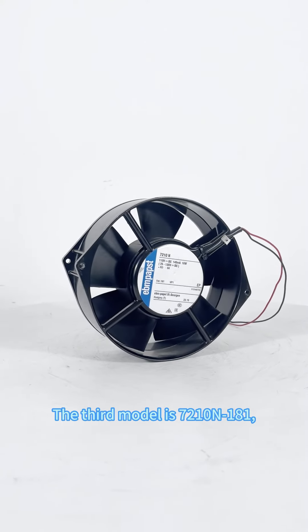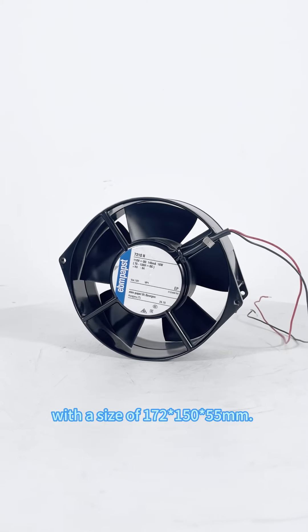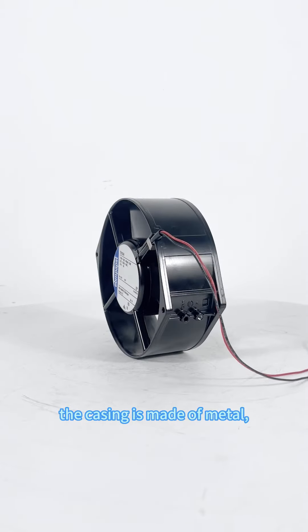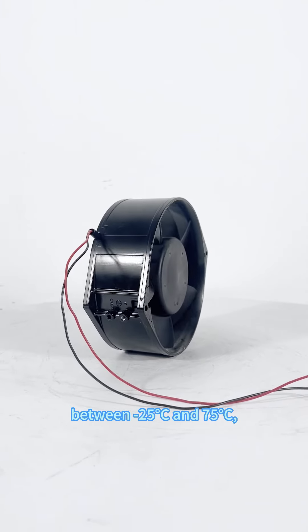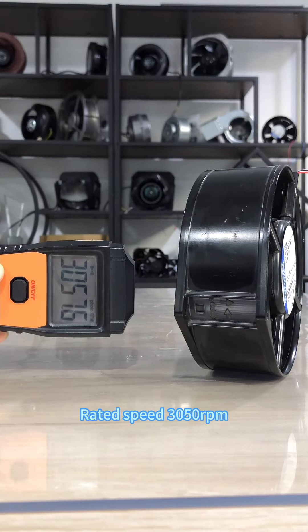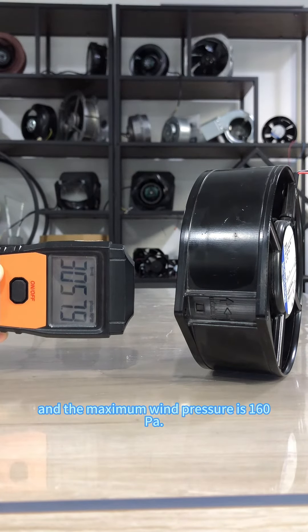The third model is 7210N-181 with a size of 172 by 150 by 55 millimeters. The impeller is made of plastic, the casing is made of metal, with ball bearings. The operating temperature is between minus 25 degrees and 75 degrees Celsius and it has stall protection. Here are its parameters: rated voltage 110V, rated current 0.145A, rated power 16W, rated speed 3,050 RPM. The maximum air volume is 345 cubic meters per hour and the maximum wind pressure is 160 Pa.